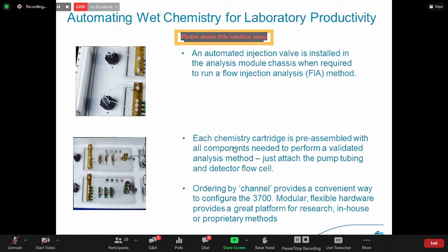And each chemistry has its own cartridge, which comes pre-assembled with all the components that are necessary to run that particular chemistry, whatever that happens to be. So if the valve is necessary, say for FIA, and depending on what detector is necessary, you swap out the cartridge and then connect your pump tubes via the pump to your reagent containers. And that way you can pull them in and out to do different types of analyses. So by ordering a channel, it offers a modular, flexible hardware design for a wide variety of different types of analyses, not just cyanide.